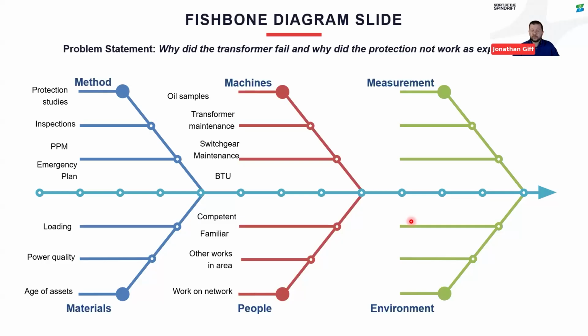One thing to touch on, Dan, which I don't think we've covered yet: was there any other work, be it electrical or non-electrical, taking place in and around the substation? If we go back to the photograph shown earlier on, the transformer compounds were quite tight to the factory floor. We had some pipe work just above where the transformer compounds were. So I'm keen to see if there were any external factors that may have influenced what happened. Yeah, it's a good point, especially for work on the network as well.